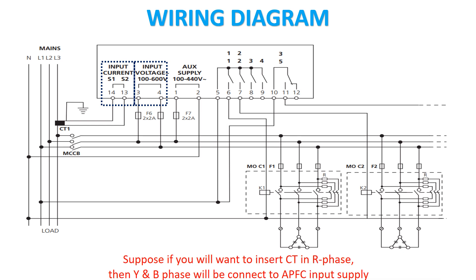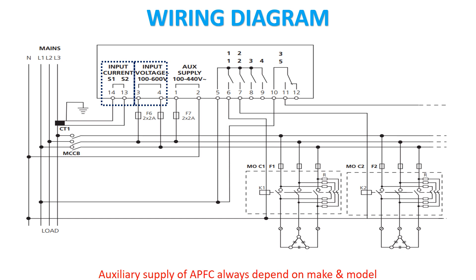Suppose if you want to insert CT in R phase, then Y and B phase will be connected to APFC input supply. Auxiliary supply of APFC always depends on make and model, so always check the auxiliary supply of APFC carefully.